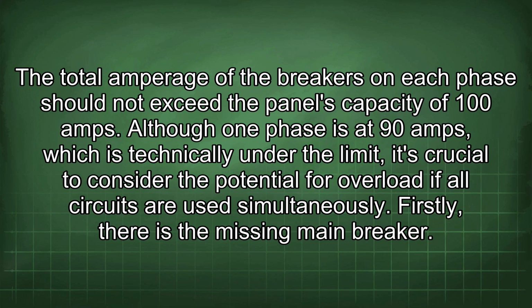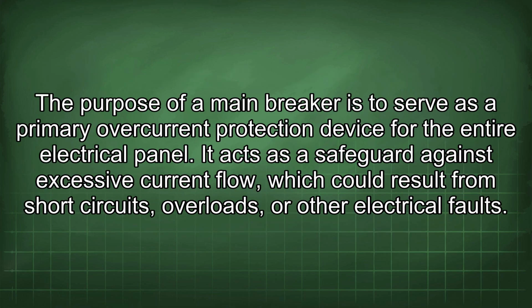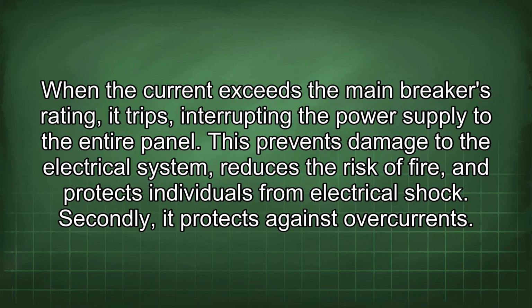Firstly, there is the missing main breaker. The purpose of a main breaker is to serve as a primary overcurrent protection device for the entire electrical panel. It acts as a safeguard against excessive current flow, which could result from short circuits, overloads, or other electrical faults. When the current exceeds the main breaker's rating, it trips, interrupting the power supply to the entire panel. This prevents damage to the electrical system, reduces the risk of fire, and protects individuals from electrical shock.